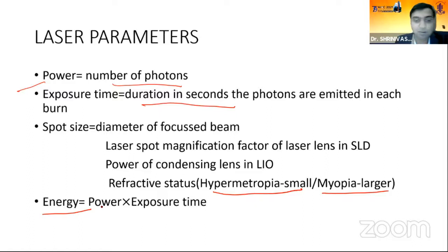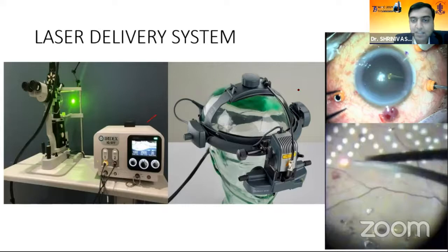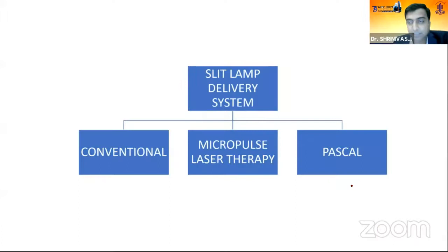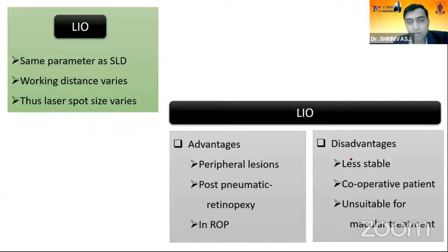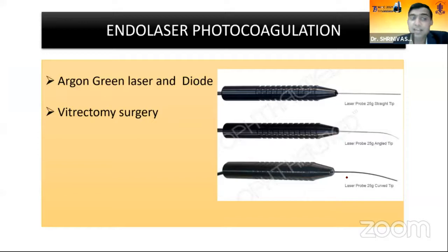The various laser delivery systems include slit lamp-based delivery, the laser indirect ophthalmoscope (LIO), and the endo laser used during vitrectomy. Slit lamp delivery has evolved from conventional to multi-spot laser and micropulse laser therapy, with the pattern scan laser first coined as PASCAL. LIO advantages include treating peripheral lesions, post-pneumatic retinopexy, and ROP cases, though it is less stable and requires a cooperative patient. Endo photocoagulation uses green and diode lasers.